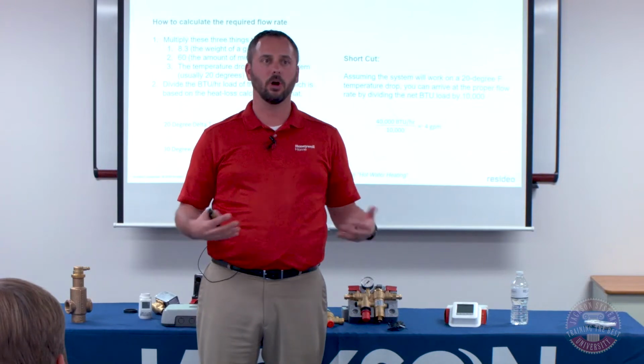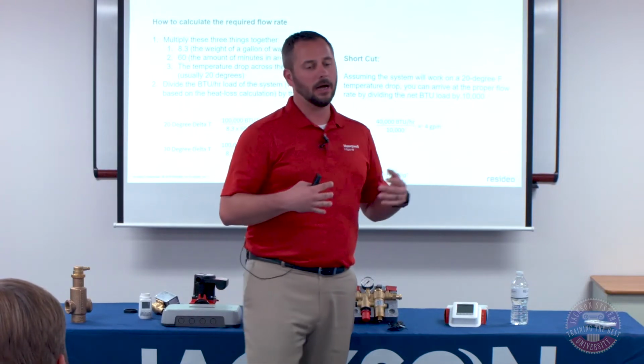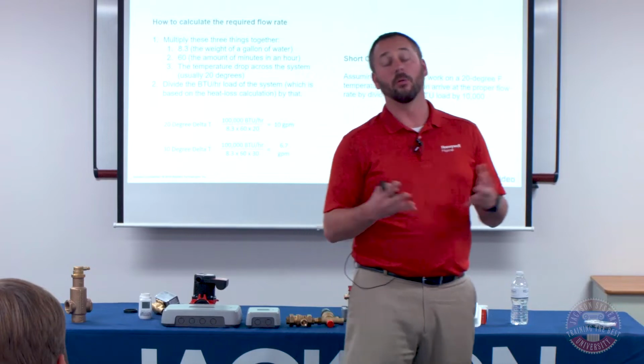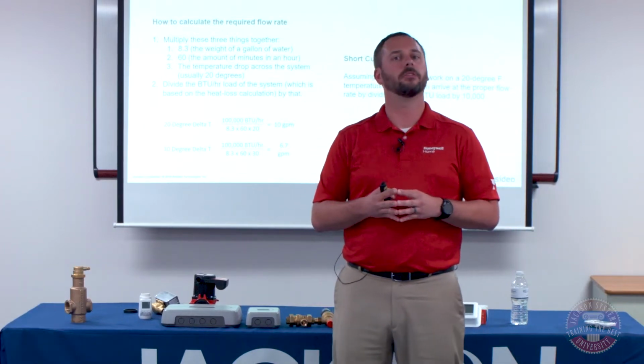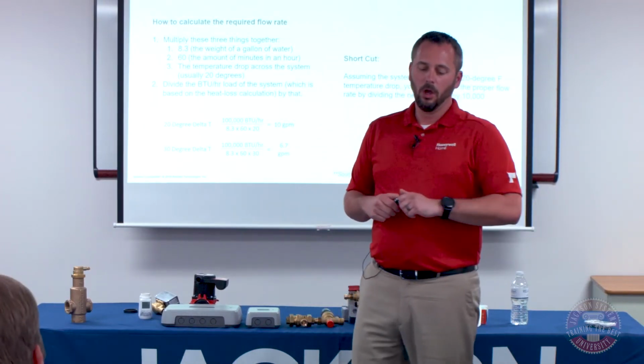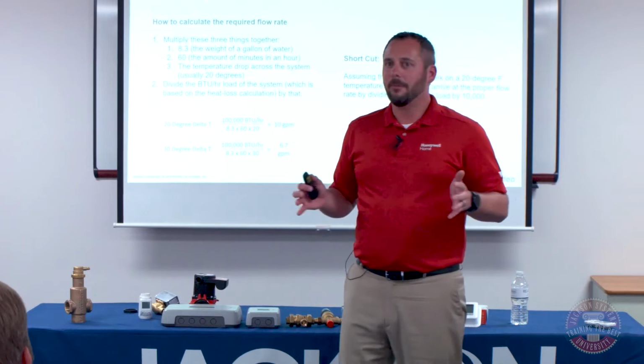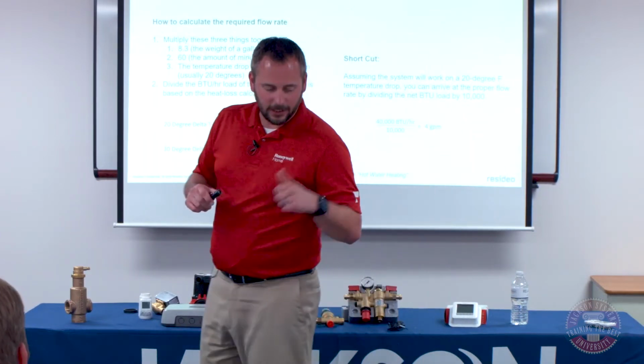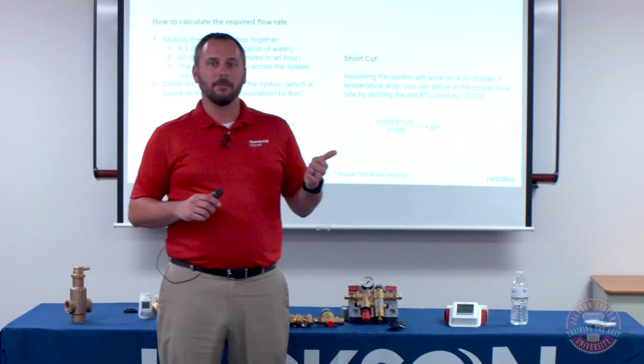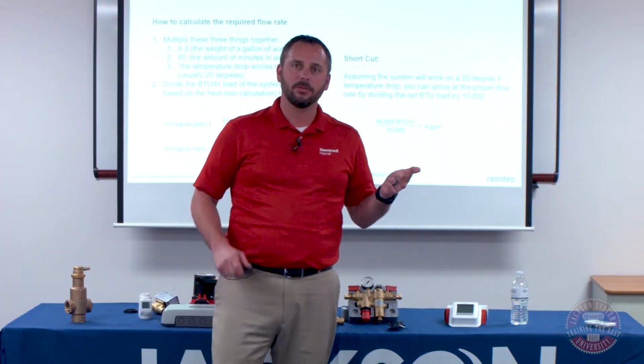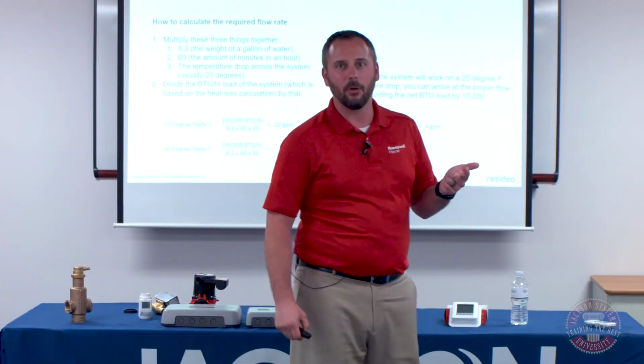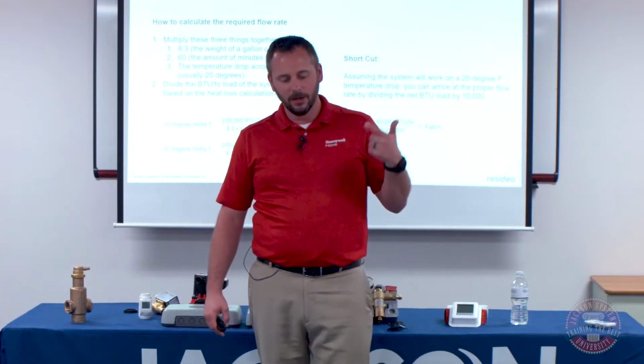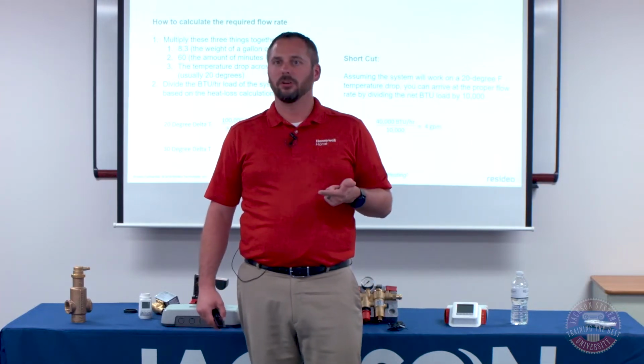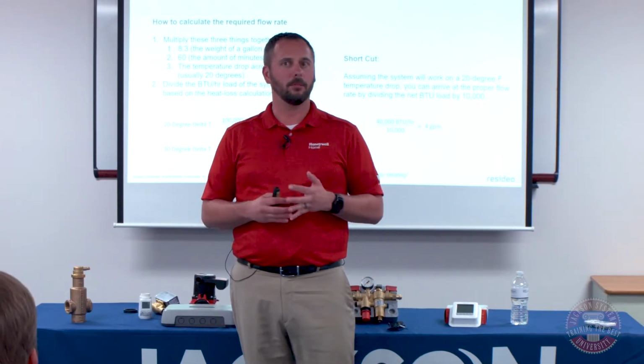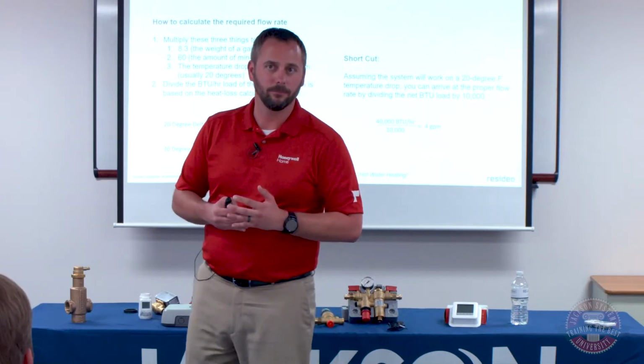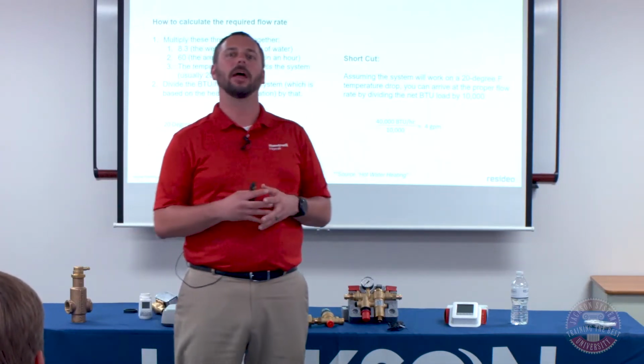So if you designed your flow rates, et cetera, to handle that, the colder the water, the better. But a lot of that depends on the system design. So to come up with the formula, if you want to do the math out, you're going to multiply the weight of a gallon of water, which is 8.3, by the number of minutes you have in an hour, which is 60, times the temperature differential you want to use. So in the first example, I'm going to use a 20-degree temperature differential, because remember I said the math is real easy on that one.